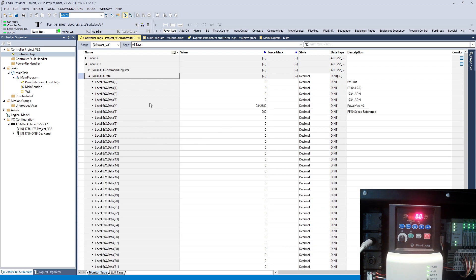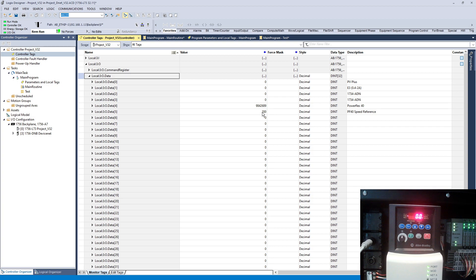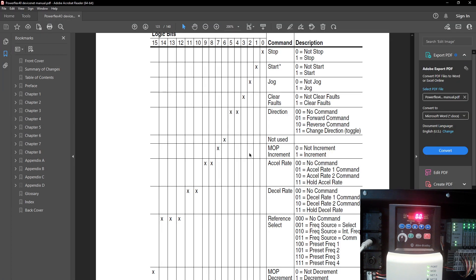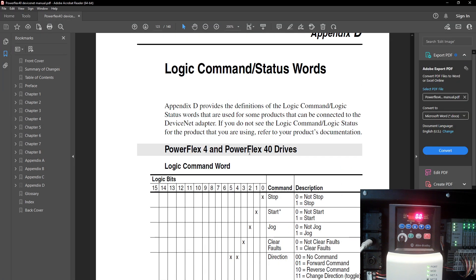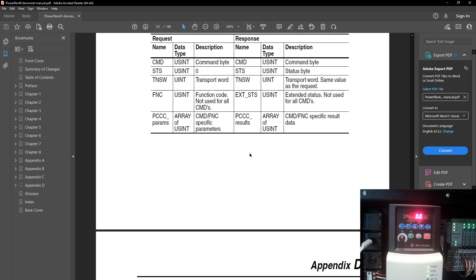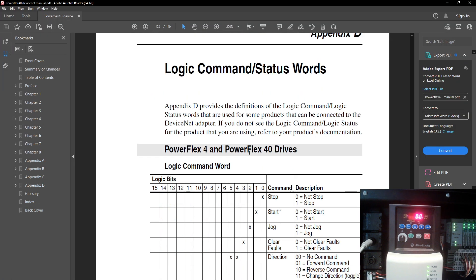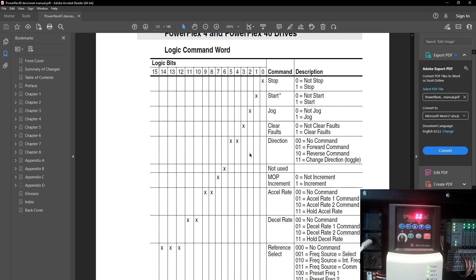Location number 5 we had another 16, so total 4 bytes we are using here. The first 16 bits according to the manual are predefined here. As you can see what their meanings are, wherever this X is means if I put one here, one command, it's going to be the stop command going into the VFD.